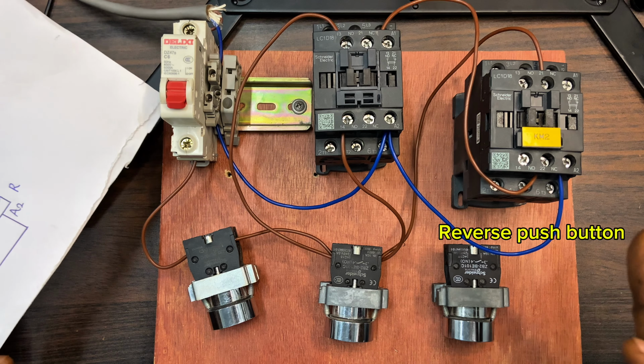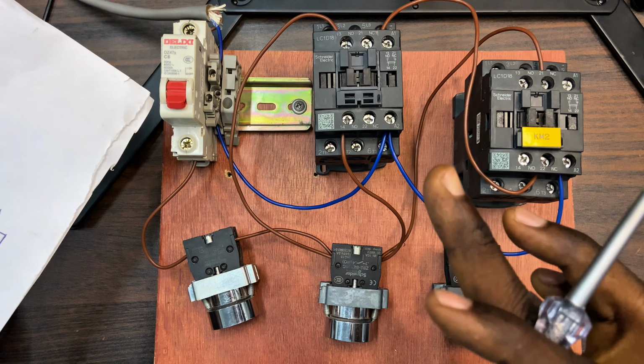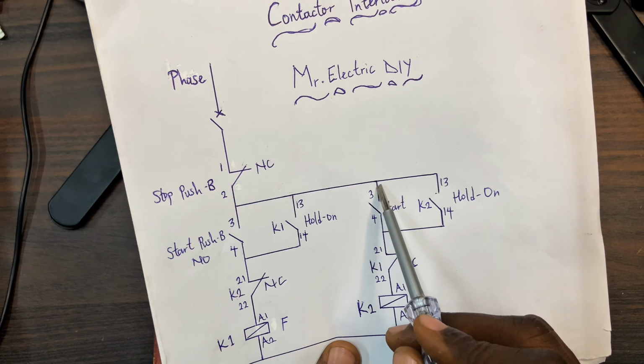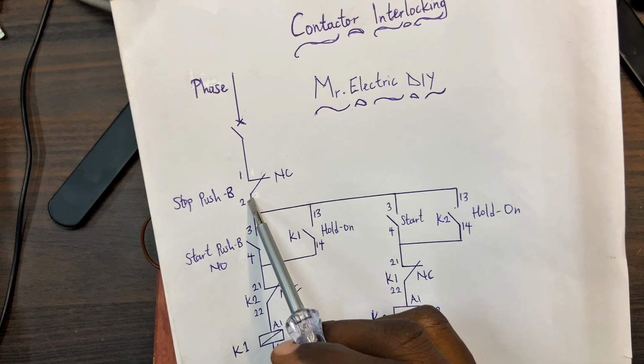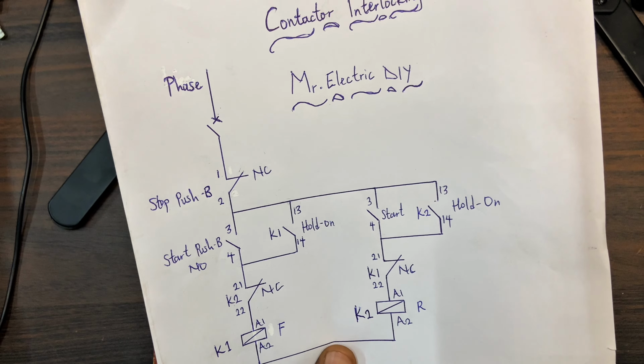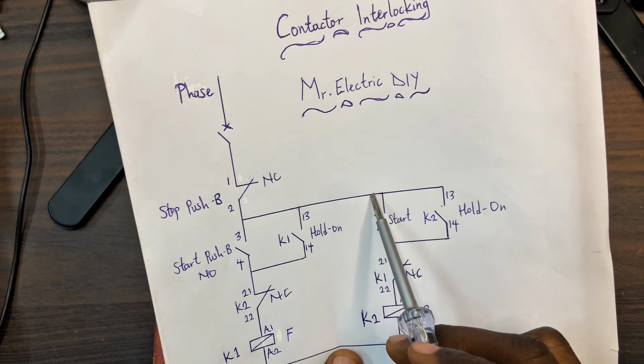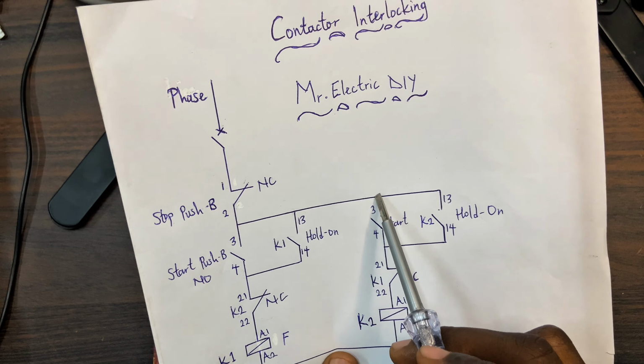What we have to do to the push button is to connect a live signal to it. And you could see that in the wiring diagram, there's a live from number 13 to number 3. This is the start push button. There's a live from this side to this side. You can also pick the live from number 3 to this side, number 3. It is the same thing. Or number 2 to number 3. It is the same thing. I can just cancel this wire or this line you see here and then take it to number 3 or even take it to number 2. It is the same principle. And we are going according to the wiring diagram.